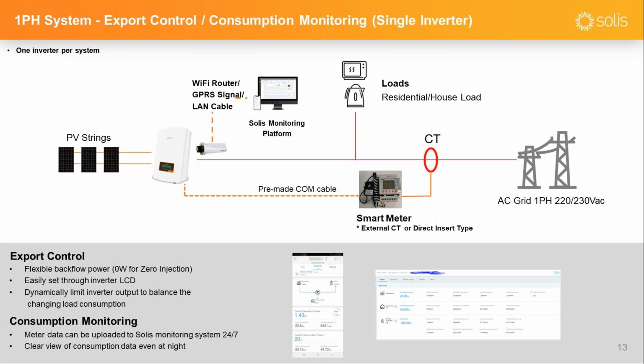So on the monitoring system, you are able to see the inverter's generation and also the load consumption of your house. And then you are also able to see the power flow at the grid connection point, which is where you install the meter. So that you can have a very clear picture of how your system's power flow is going forwards or backwards.